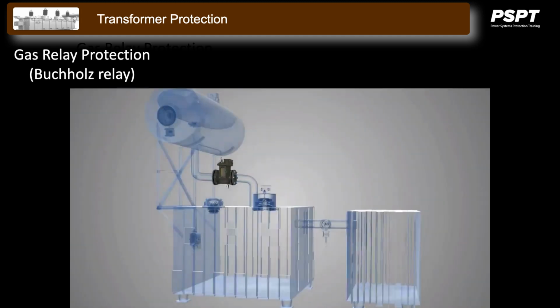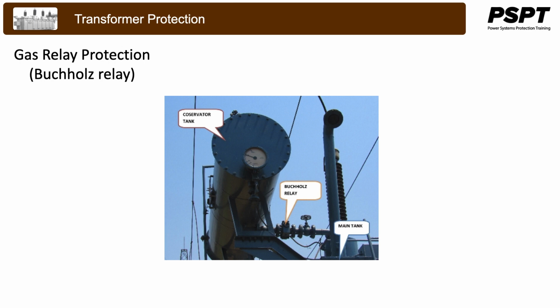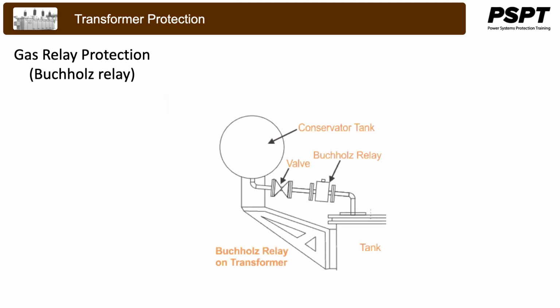The Buchholz relay is located in the oil line that connects the conservator tank and the main transformer body. This position above the main tank allows it to accumulate any and all gases formed and rising in the transformer. Also, any pressure surges that occur will pass through the oil connection line on the way to the conservator tank.